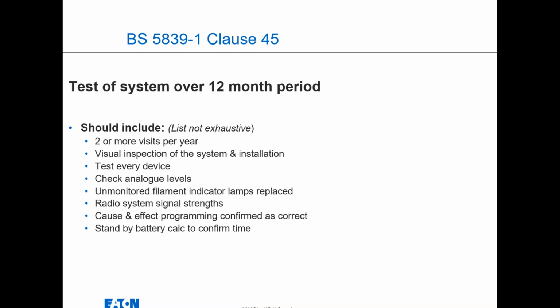So again, testing over a 12-month period, 2 visits a year, visual inspection. You must test every device. If it's an analog system, you need to check the analog levels to make sure the detectors aren't too dirty and the analog levels aren't high, otherwise you're going to have problems with false alarm issues. Radio systems, check signal strength, cause and effect programming, everything works basically, and the standby calculation to make sure the batteries are in good shape too.